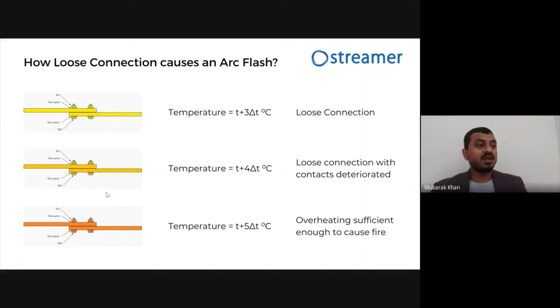Okay. After that, if the temperature is increasing again, there will be immense overheating which can cause the metal to become red hot. Then if it heats further, at 1100 degrees Celsius, the copper bus bar, if there is a copper conductor or a bus bar, the copper will melt. At 700 degrees Celsius, aluminum will melt. Okay, so aluminum has a very low short circuit capacity or low mechanical strength as compared to copper. So at 700 degrees Celsius, the aluminum will melt. At 1100 degrees Celsius, copper will melt.